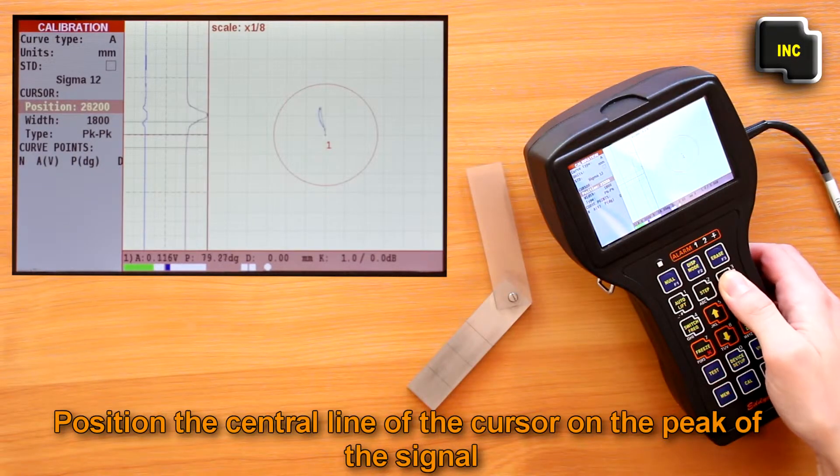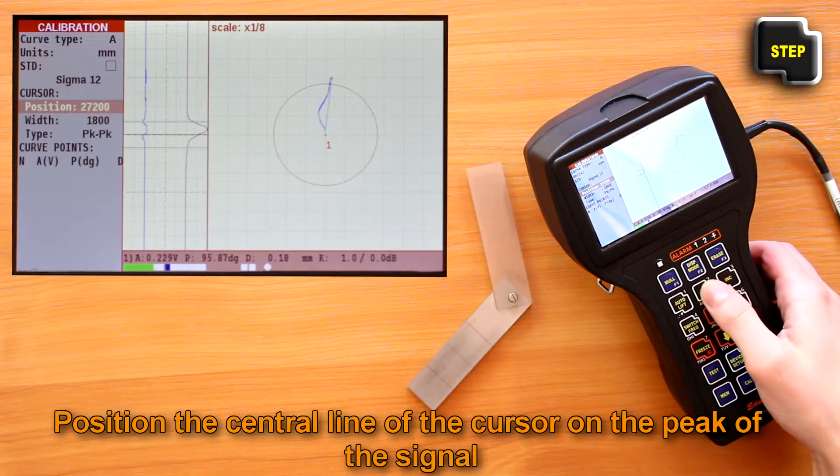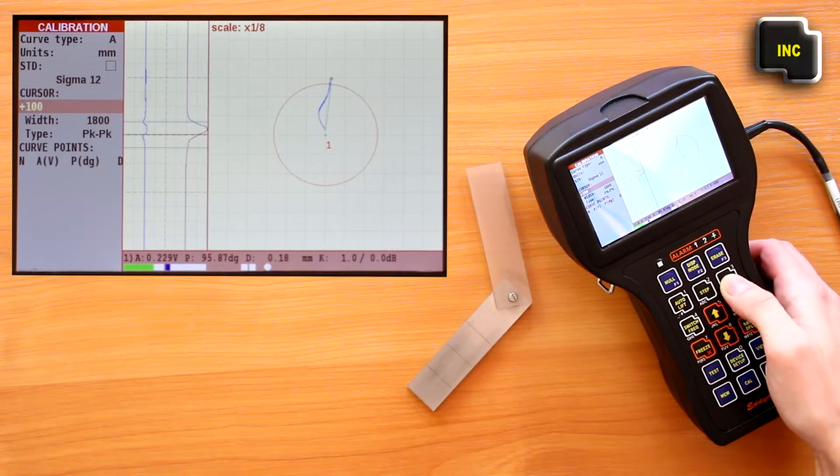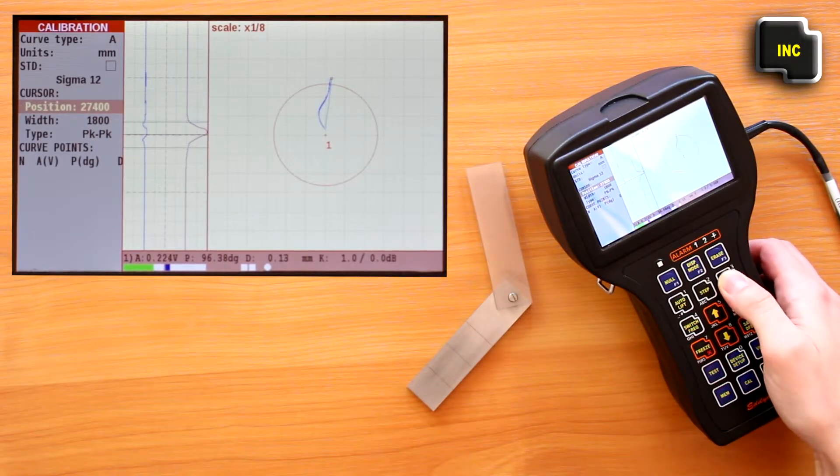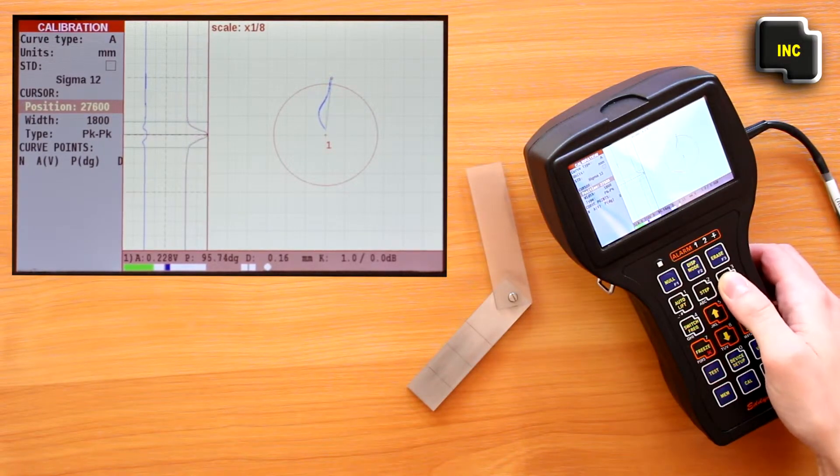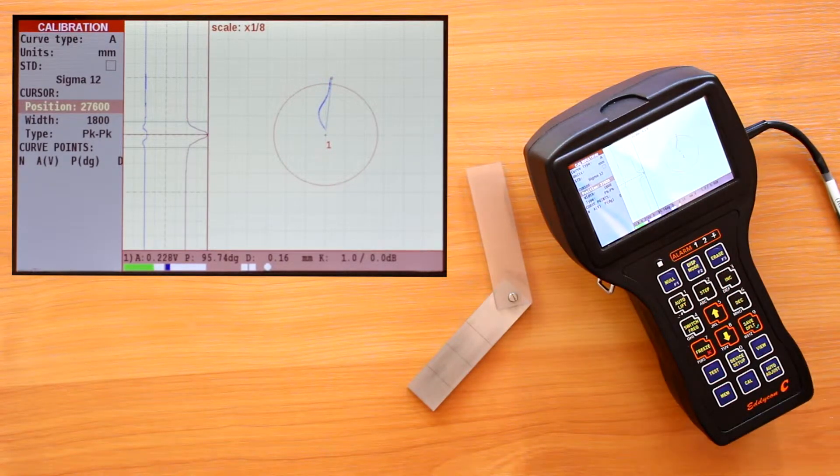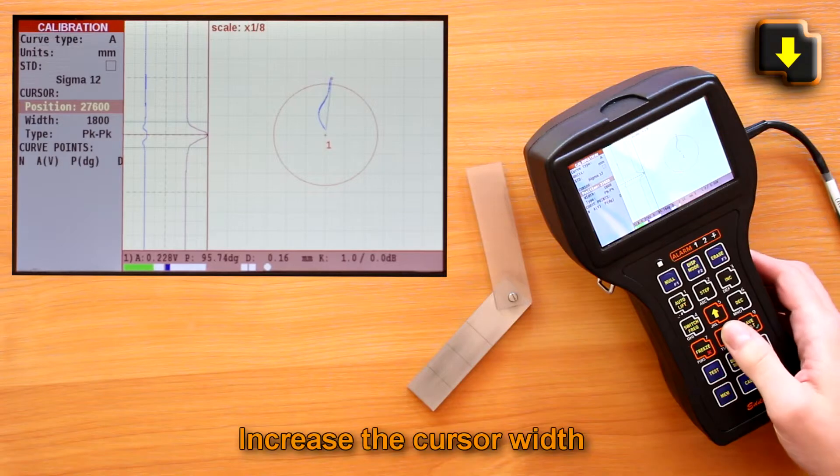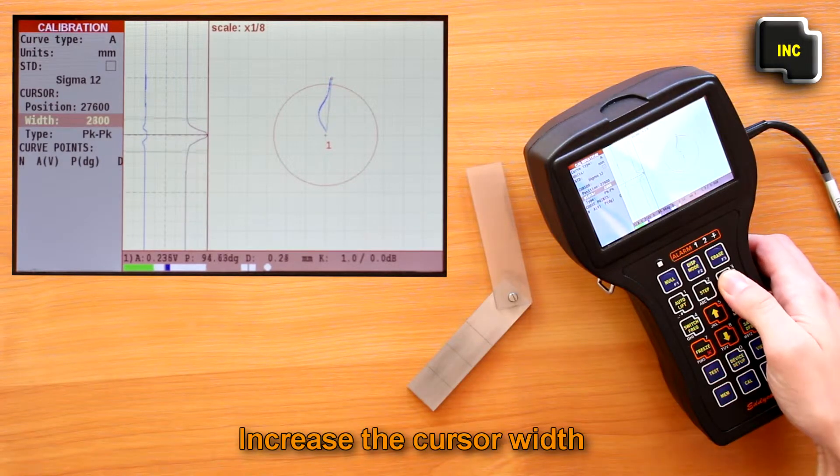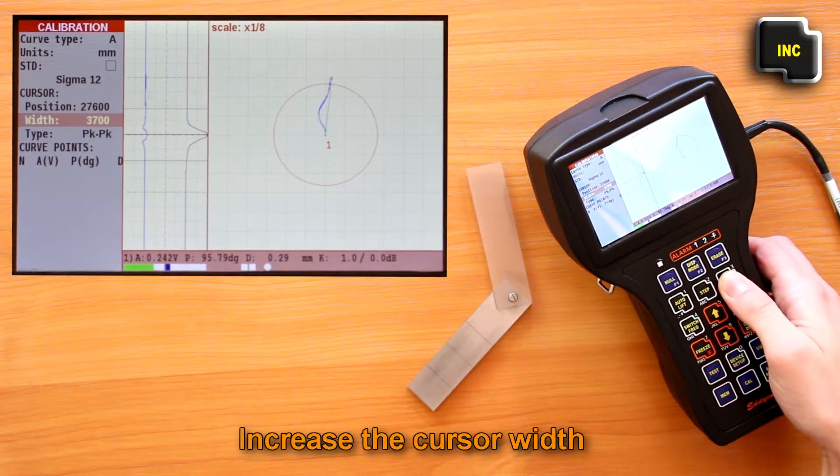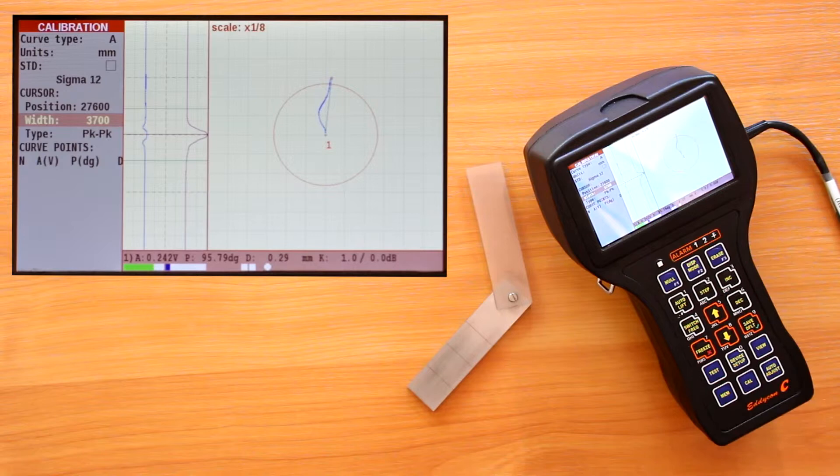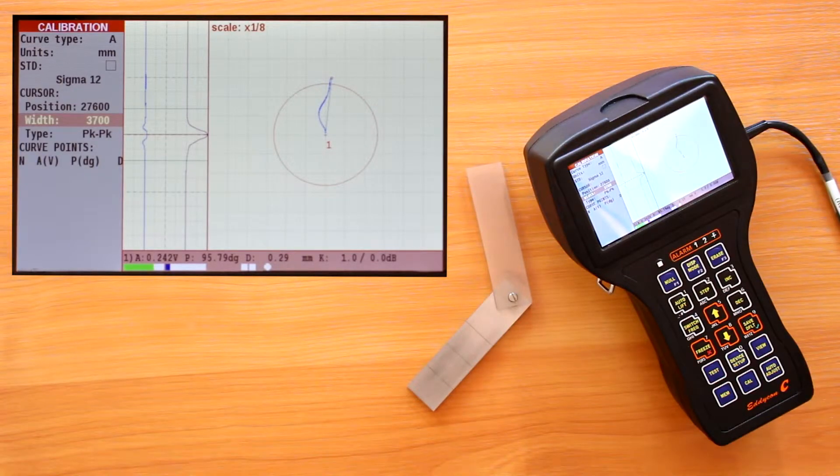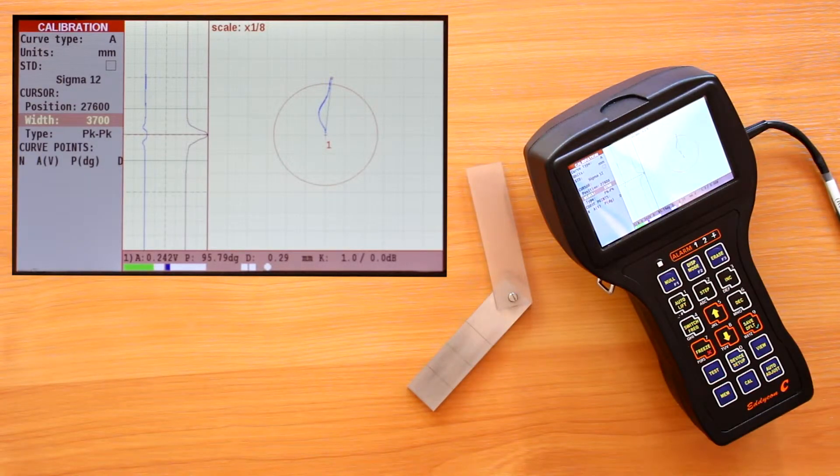Using the width item, increase the cursor width to get only one signal there—that is, the signal from the defect. Having placed the cursor on a defect, press the save defaults key in order to add the calibration curve point.